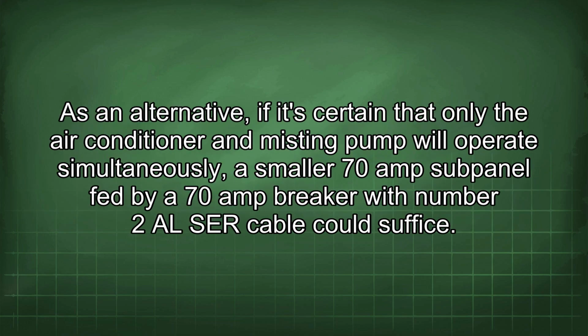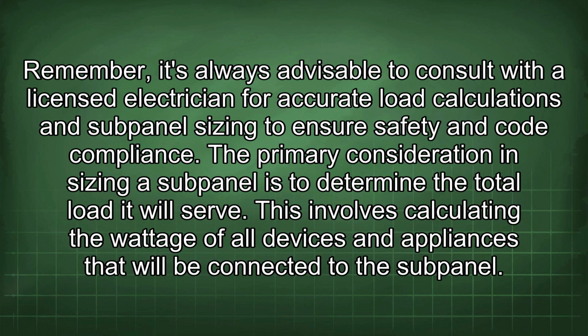As an alternative, if it's certain that only the air conditioner and misting pump will operate simultaneously, a smaller 70 amp subpanel fed by a 70 amp breaker with number 2 AL SER cable could suffice. Remember, it's always advisable to consult with a licensed electrician for accurate load calculations and subpanel sizing to ensure safety and code compliance. The primary consideration in sizing a subpanel is to determine the total load it will serve.